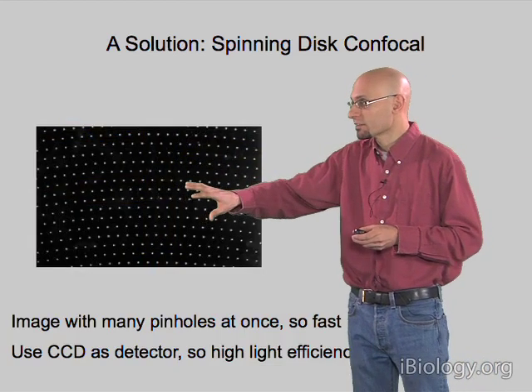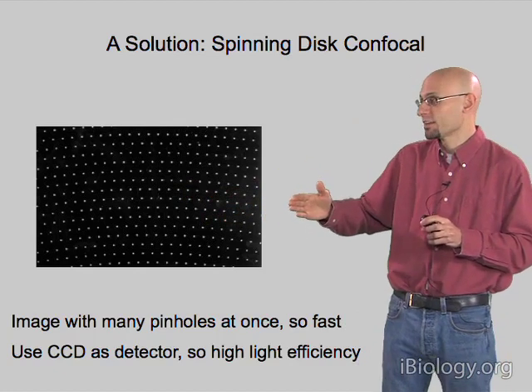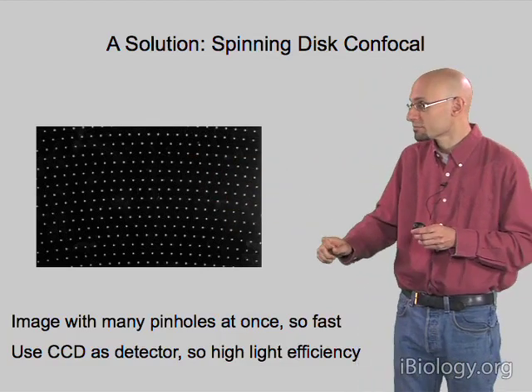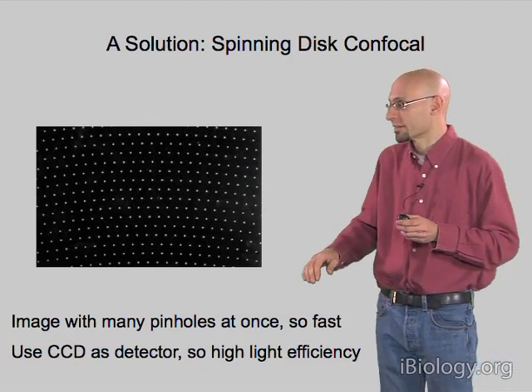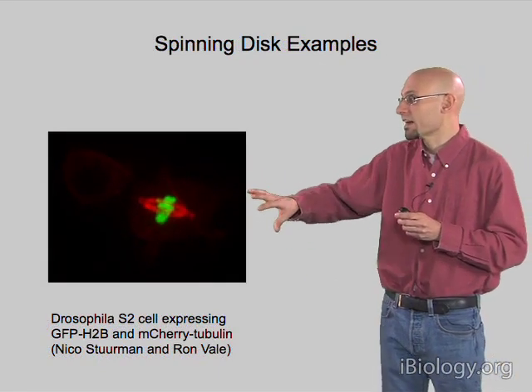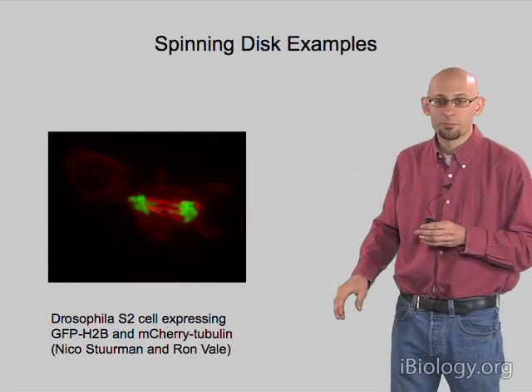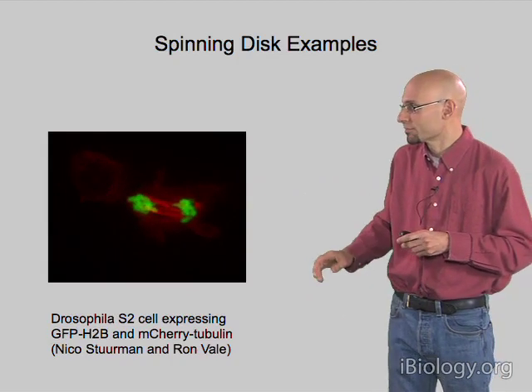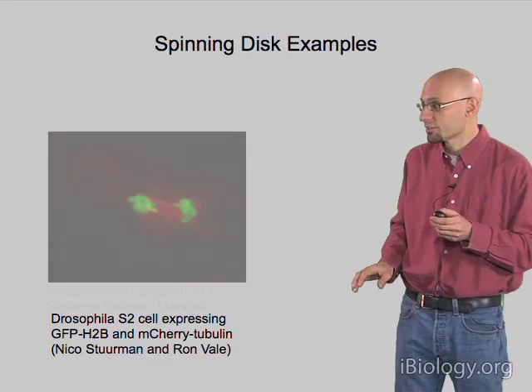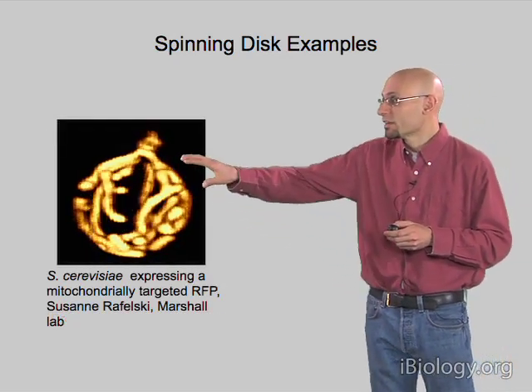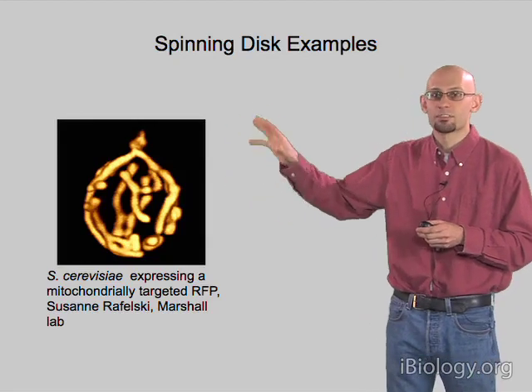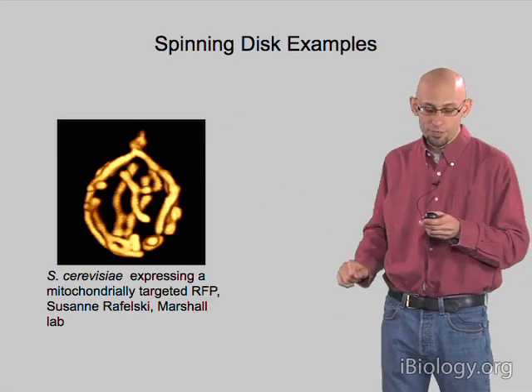Here is an image I took of our spinning disk with the disk parked, just shining light through it — you can see the pinhole grid of this piece of the disk, and it rotates such that these pinholes sweep out over every point in the sample once and only once. Here's an example of a movie acquired with a spinning disk confocal — a time-lapse movie of a dividing Drosophila S2 cell, about 15 minutes compressed to a few seconds. Because they're fast and high light efficiency, spinning disks are very good for live samples. Here's also a 3D reconstruction of a yeast cell expressing a mitochondrially targeted RFP.